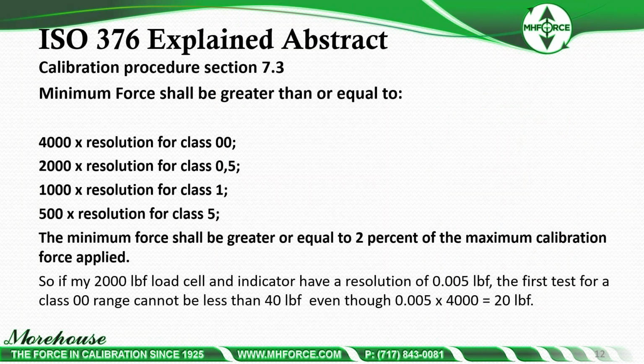Some other things about ISO 376, minimum force. ISO 376 uses a class system. If you're familiar with ASTM, they have class AA and class A ranges. ISO has four ranges, and these ranges are based on multiples of the resolution. The minimum force shall be greater than or equal to 4,000 times the resolution for class 00, 2,000 for class 0.5, 1,000 for class 1, 500 for class... that should be class 2. I got a mistake here. But 500 for class 2.